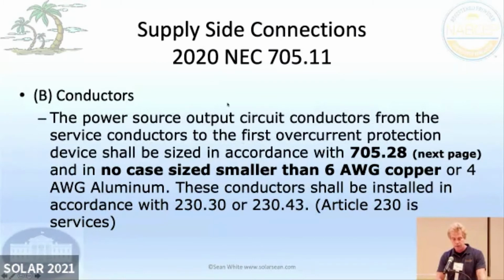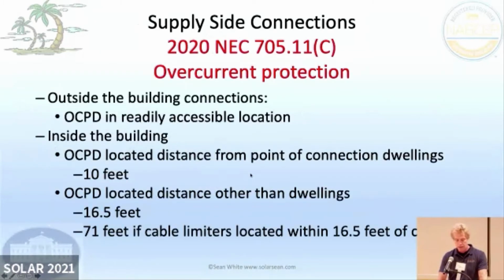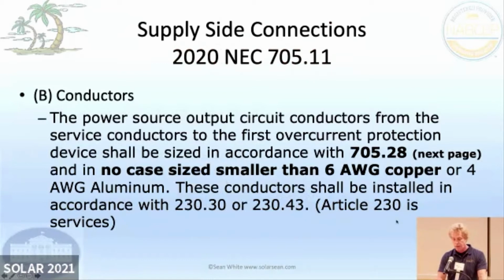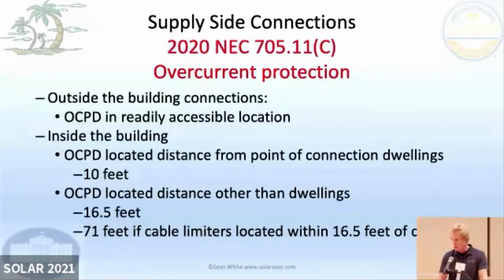Here's just some for supply side connections. New rules for 2020: we have a minimum wire size, so 6-gauge copper or 4-gauge aluminum. The wires can't be too small. That makes sense. And we need to comply with Article 230. That might change a little bit too, but we're going to ground it like a service for sure. In an earlier version of supply side connections, you could ground it like a service or not, just different interpretations of that. And here it's pretty plain and clear to ground it like a service. So bond neutral to ground separately. And that might change back to the other way where you could go either way.